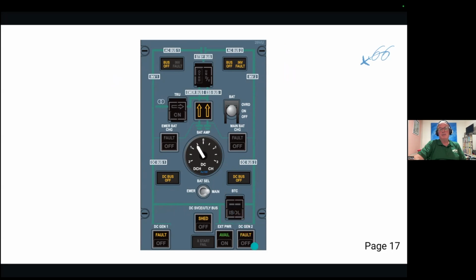But at any time, if you lost number 2 generator, for example, therefore number 2 DC system, through operation of this bus tie contactor, number 1 DC would supply number 2 bus. So it's really all automatic - no switching has to be done in terms of bringing buses back to life.